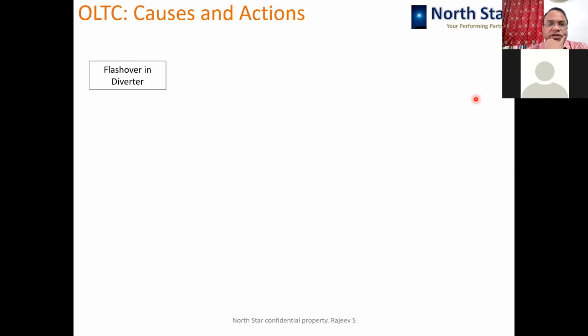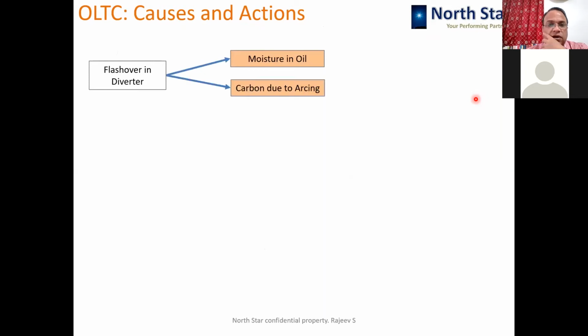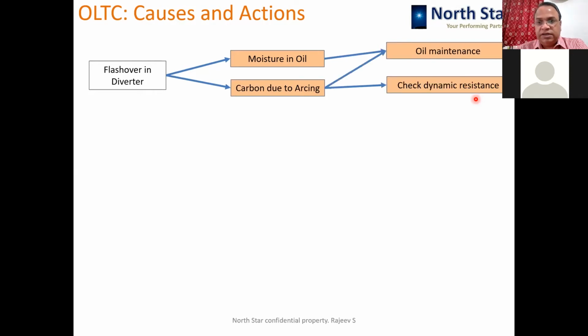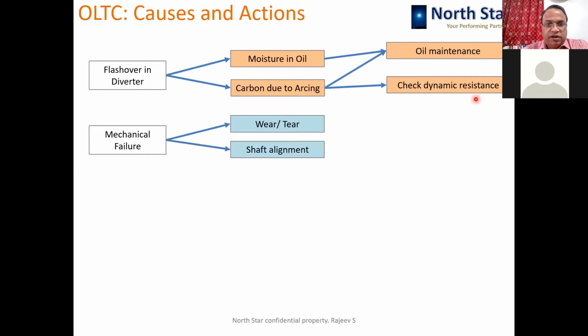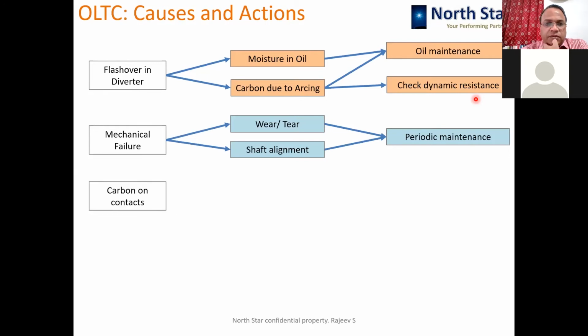So OLTC causes and actions: number one, when it is an in-tank OLTC, there is a flashover in the diverter switch. The excessive flashover happens because of moisture in the oil or carbon due to arcing. So with moisture in the oil, of course, oil maintenance is required, and if the dynamic resistance is getting deteriorated, then also arcing increases and carbon gets formed. Second is mechanical failure because of wear and tear, and there could be disturbances in the shaft alignment, and that can cause severe arcing in the OLTC, which can lead to failure. So the key to this is periodic maintenance of the OLTCs.